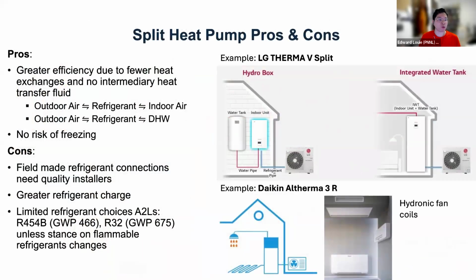So on the split heat pump combi heat pump systems, you can see one of the pros is there is not that intermediate heat exchange fluid. So we can go from refrigerant straight to indoor air, or refrigerant straight to the domestic hot water. So there's some greater efficiencies there. If the intermediate fluid is not glycol, and it's water, then there is a risk of freezing. But in the split heat pump systems, since it's refrigerant going to the outside, there's really no risk of freezing.